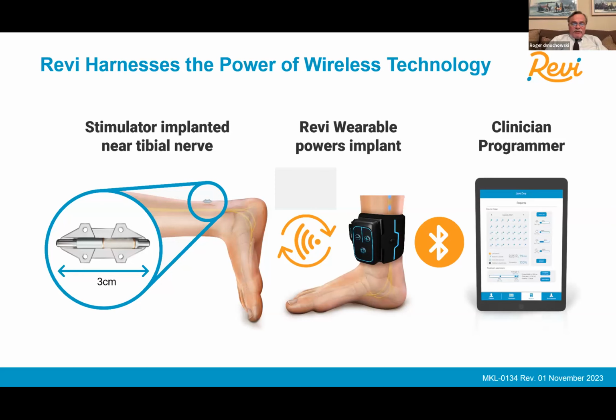The second part of the device is the central component of the slide, which is the wearable, which allows the patient to apply the energy that is received by the device through essentially Bluetooth RF transmission. The external wearable can be worn at patient discretion, and for the purposes of the clinical trial was worn twice a day for 30 minutes, and we had greater than 90% compliance with that. The external wearable is where the power source is for the device, and it feeds into the implantable that Cindy just commented on, and we'll talk more about in a second.